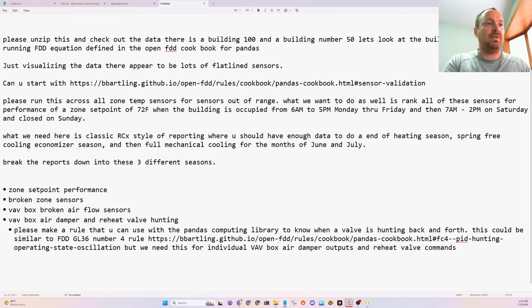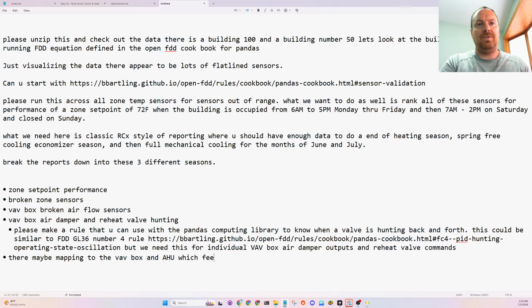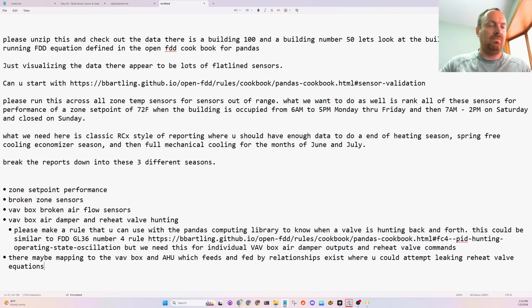Let's see, what else could we do with a VAV box? There may be mapping to the air handling unit and VAV box, where feeds and fed by relationships exist, where you could attempt leaking reheat valve equations. I think that's good enough for VAV boxes. Maybe we should start there.